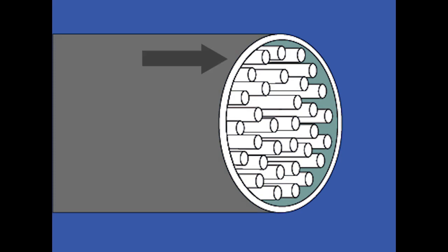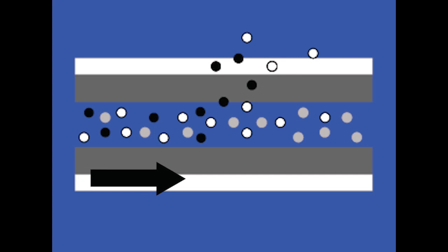The hollow fiber membrane consists of a series of narrow, semi-permeable tubes in a porous membrane. As compressed air travels through the fibers, oxygen and water vapor permeate the membrane and are vented off, leaving a stream of high purity nitrogen gas.